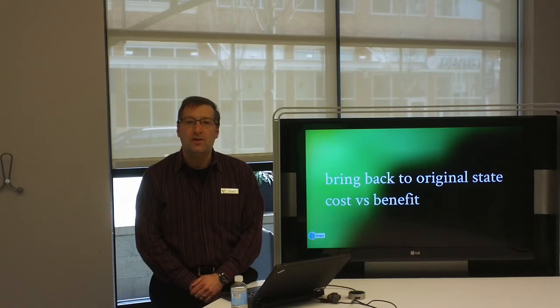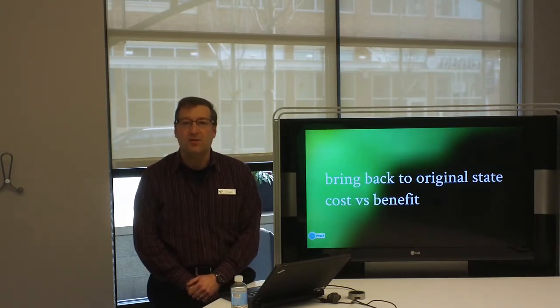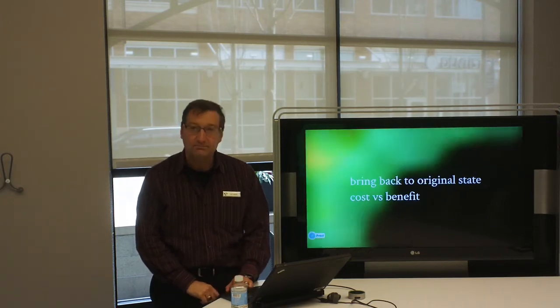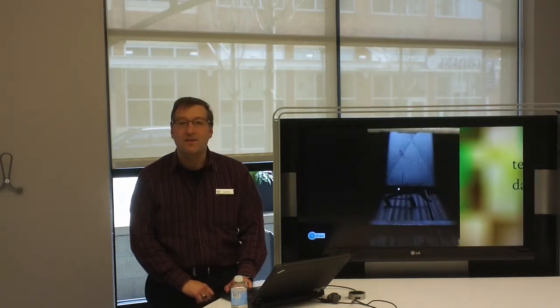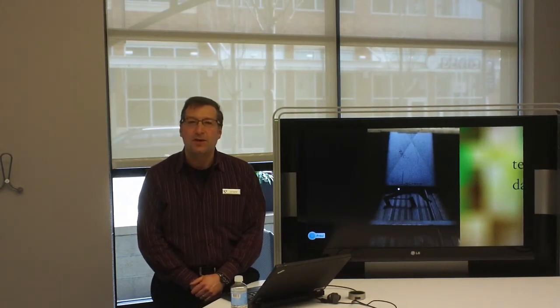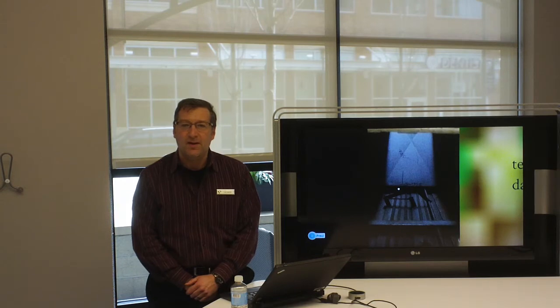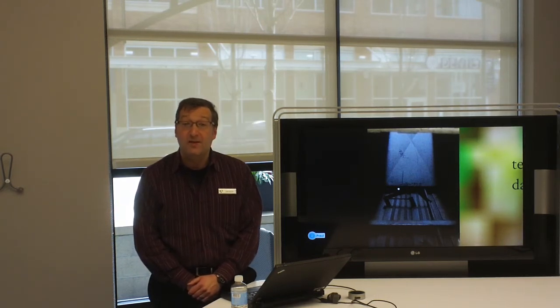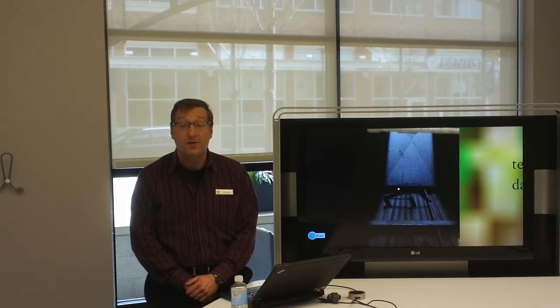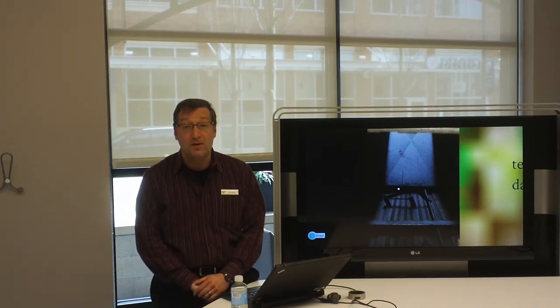The first thing that we looked at as a team was what it would take to bring the air handler back to its original state or design conditions, and the cost versus the benefits. Some of the challenges we observed when we were looking at Air Handler 2 were that the dampers appeared to be oversized, in which case we would get much more than 20% of the outside air if we were at 20%.